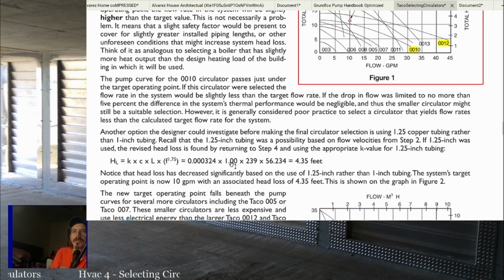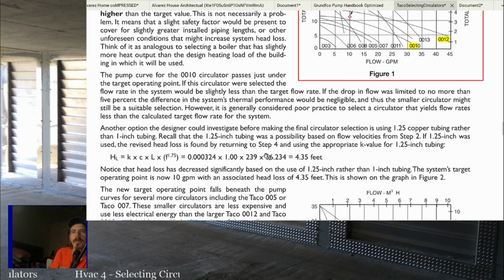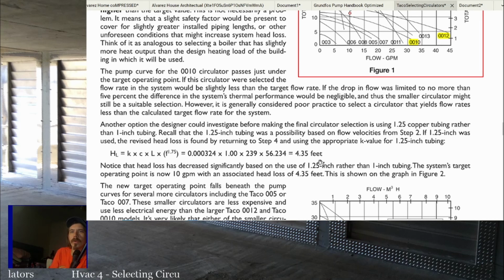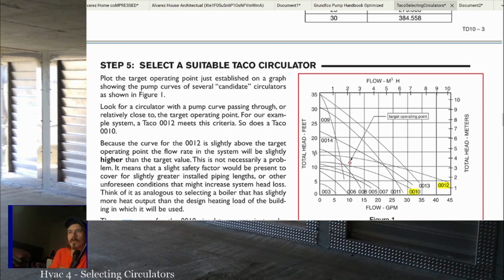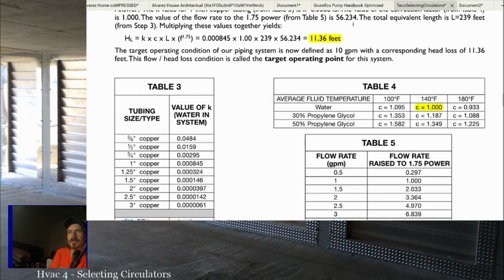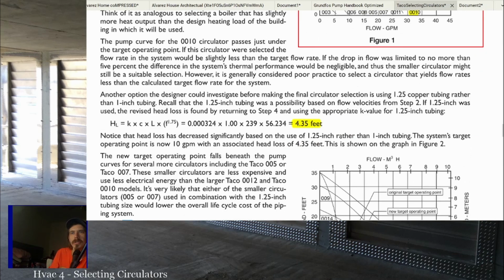So you plug in the number for 1.25 inch, times 1 times our 239 feet times our 56.234. You can plug in that new number and say, okay, the head loss decreased significantly because we're using 1.25 instead of 1 inch. The system's target operating point is now 10 GPM with an associated head loss of 4.35 feet. So we went from, where's that? We went from 12 feet of head, right? That's what we were at. Just double checking. Yeah, we went from basically 12 feet of head to just over 4 feet of head by going from 1 inch pipe to 1.25 inch pipe.